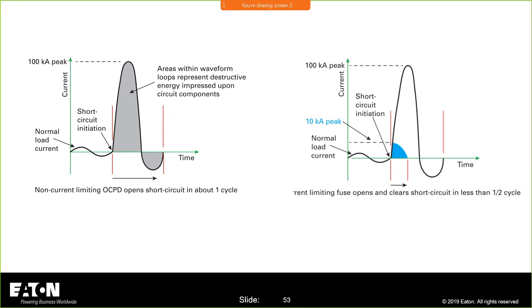And this is basically what that is doing. If I would have a fault current without a current limiting device in the picture, I'm going to see that first cycle, at least that one cycle. On a circuit breaker, I could have up to 2 to 3, maybe 30 cycles, depending upon the device, the breaker I pick. But that first hump, this is the beast. This is what provides all of the magnetic forces and heat. When I can reduce this peak to something that looks like this, I have less energy, less heat in my system, less magnetic forces than if I let this guy through.